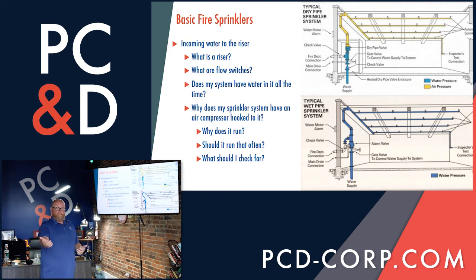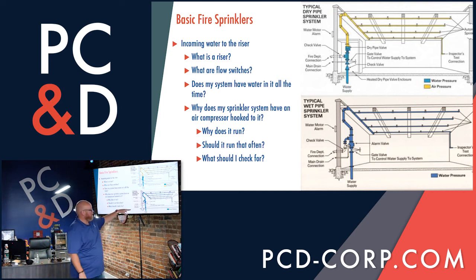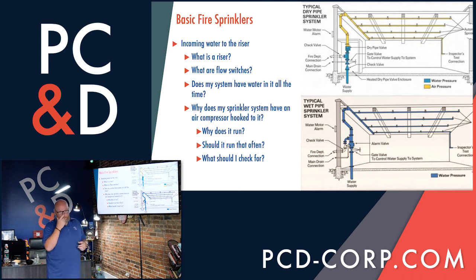You may be asking yourself, how do I know what I have? The easiest way to know if you've got a wet or a dry system is in your riser room: if you have an air compressor, it may be what's called an inline air compressor, or it may be one similar to what you have at your garage or your shop. If you have an air compressor, you have a dry system. So now that may lead you to the next question: how does a dry system function, and why would you ever have a dry system?